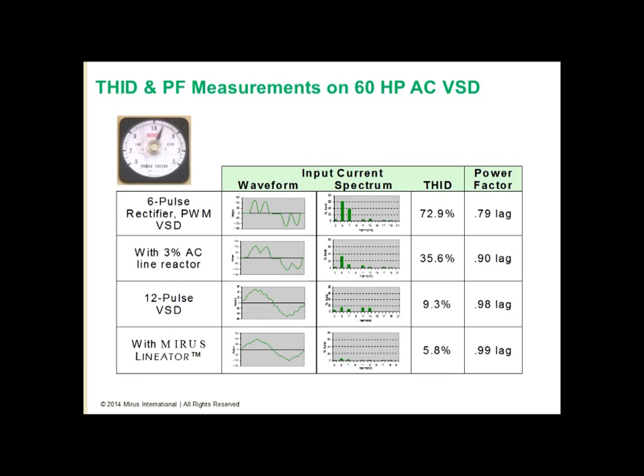This next slide shows typical nonlinear loads, so variable speed drive loads. The first row shows a 6-pulse rectifier, PWM VSD, and it shows the typical double pulsed waveform of the current. The harmonic spectrum of the current is predominantly 5th and 7th, but also contains 11th and 13th, and so on. Total harmonic current distortion of this particular load is almost 73%, and the power factor is 0.79.